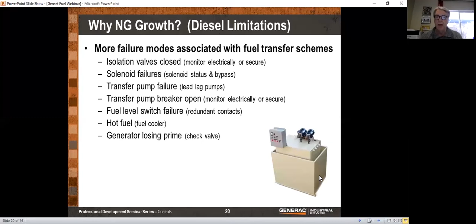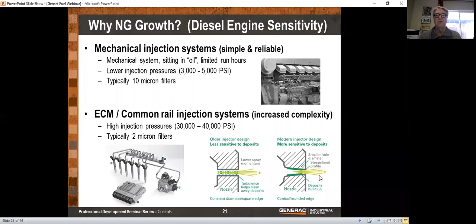If you have these transfer systems and day tanks and so on in your system, lots of things there to fail. In the newer diesel engines, we use the common rail injection systems. You get very high injection pressures, like 30 to 40,000 pounds per square inch. And that means we have to have finer filters in order to make sure that we don't clog those injectors. When you have the finer filters, then that means you're more likely to have a clogged diesel fuel filter.